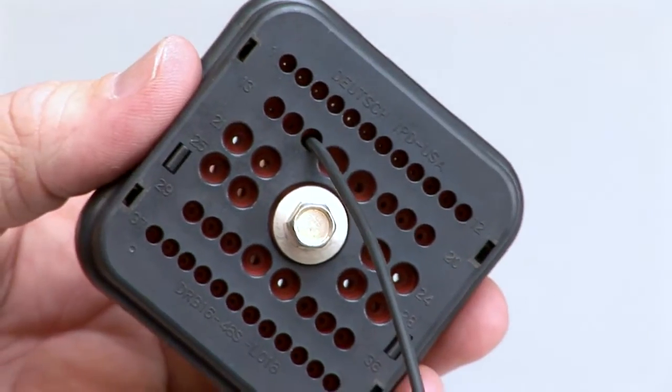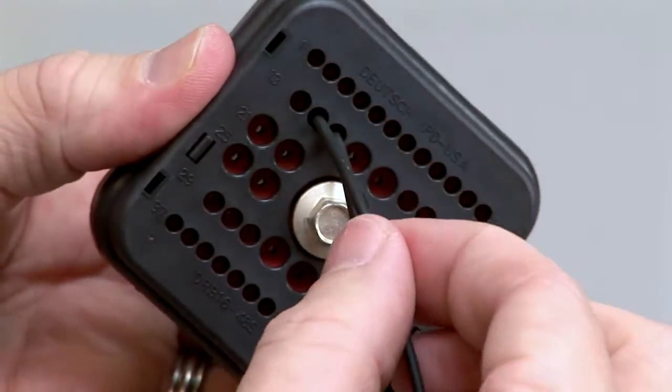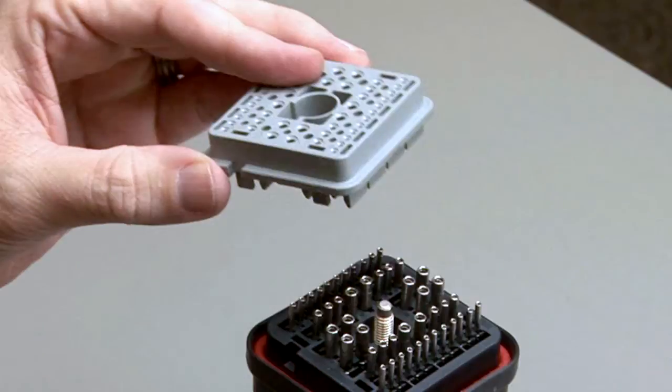Contacts should be fully inserted into the connector, with the locking fingers in place under the shoulder of the contact. Repeat this process until all of the cavities are filled. When populating a DRB series connector, secondary wedge locks are required.